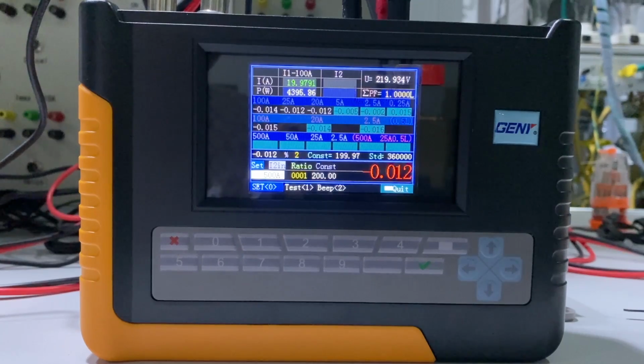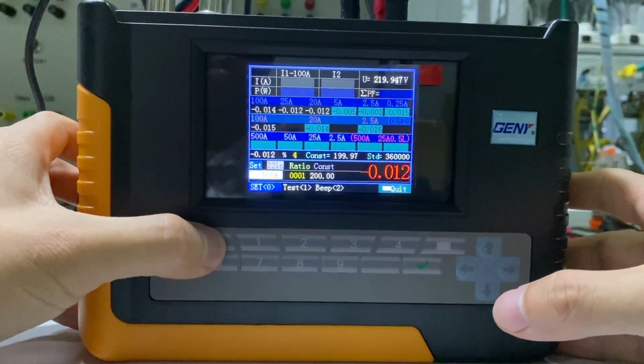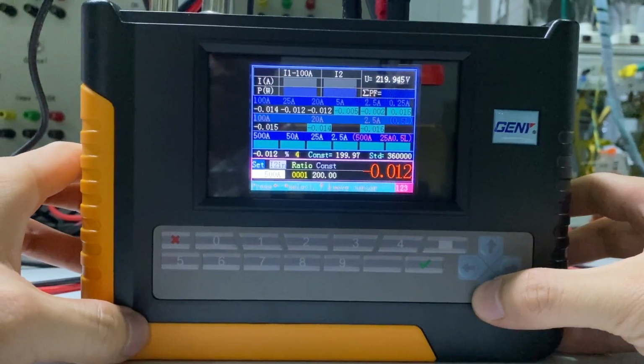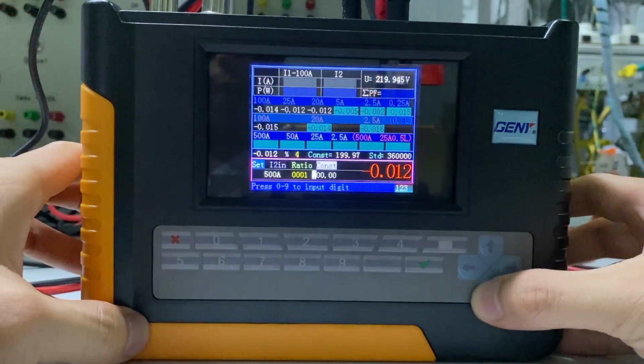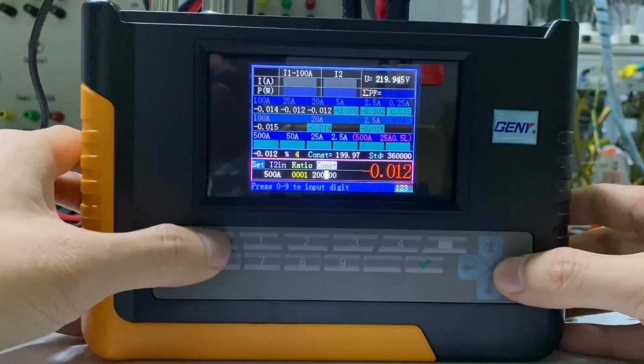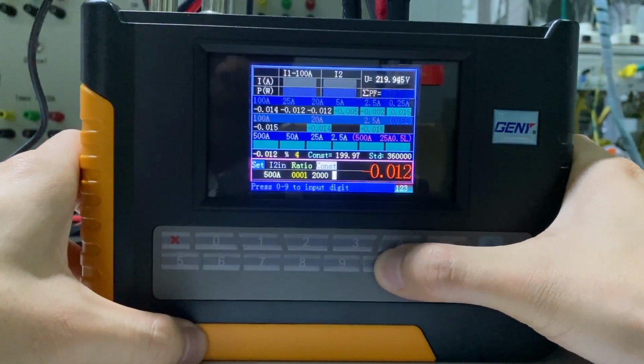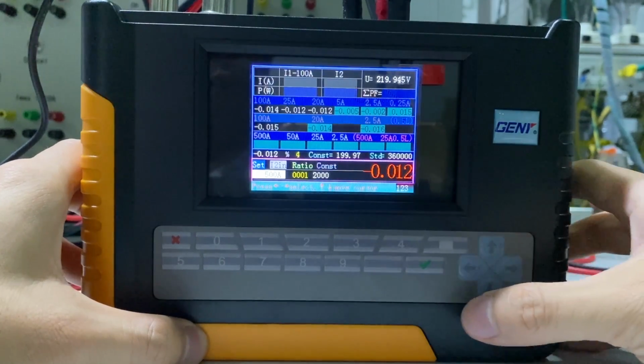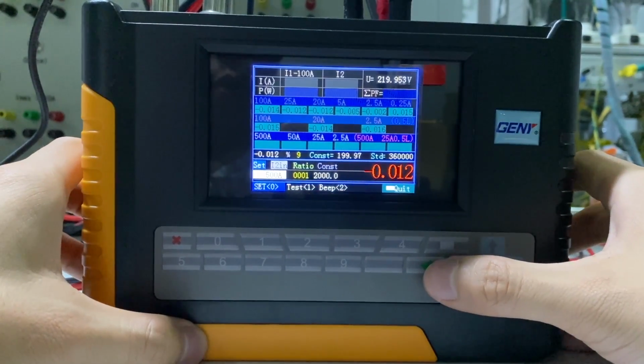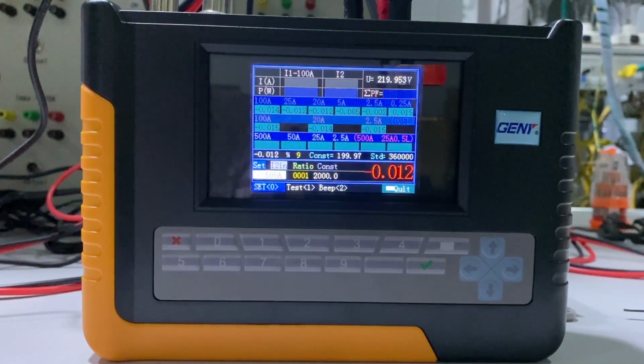The next calibration point is 5 ampere, power factor 1. The constant is set to 2000 according to the external reference meter. Stop the current first. Press 0 to activate the parameter setting area, and set the constant to 2000. Confirm the setting and resume the calibration. The calibration point is 5 ampere, power factor 1.